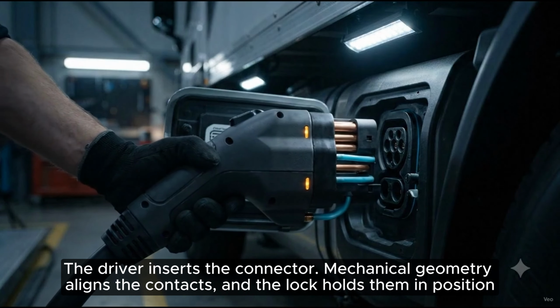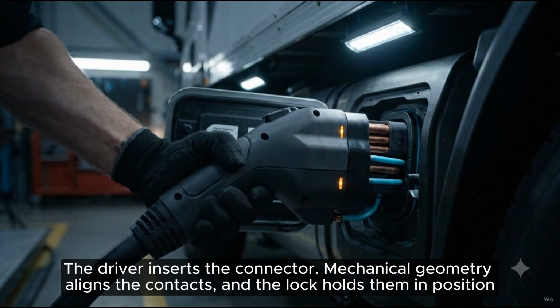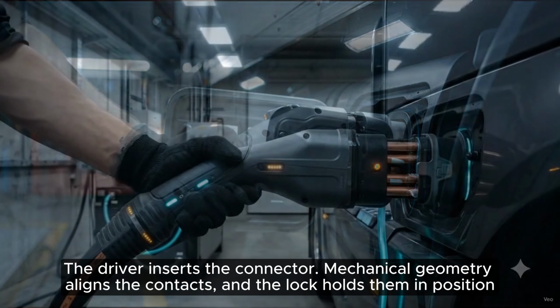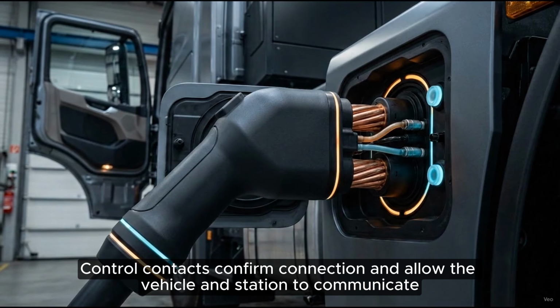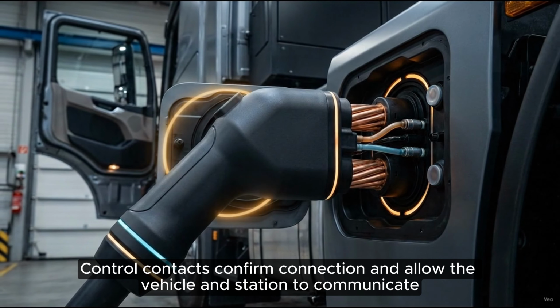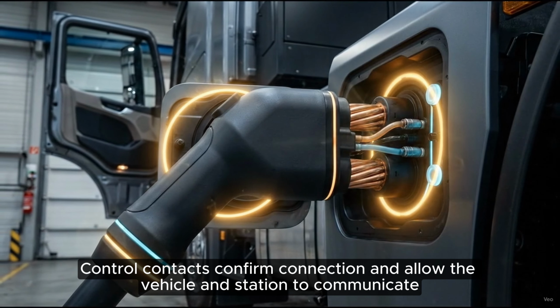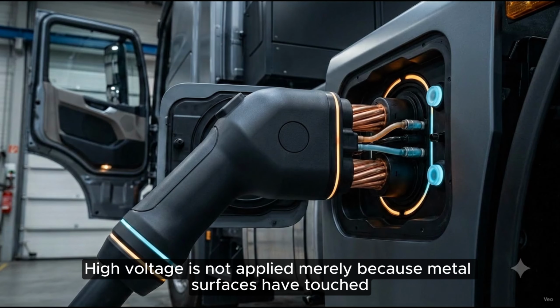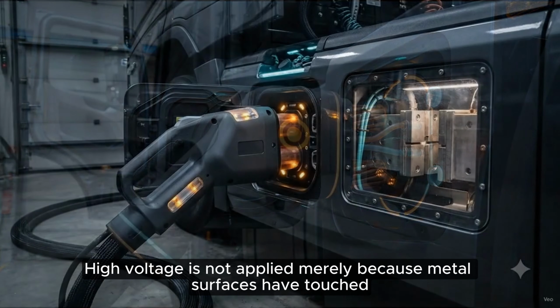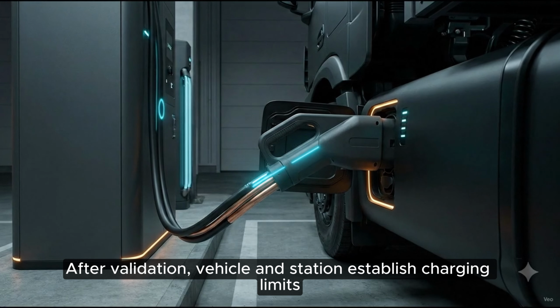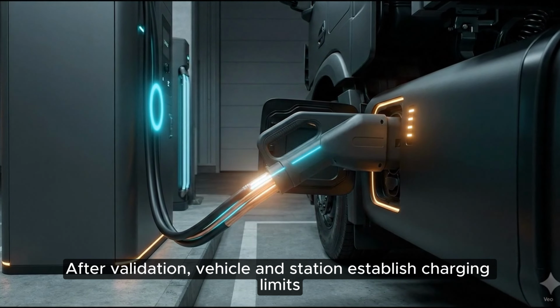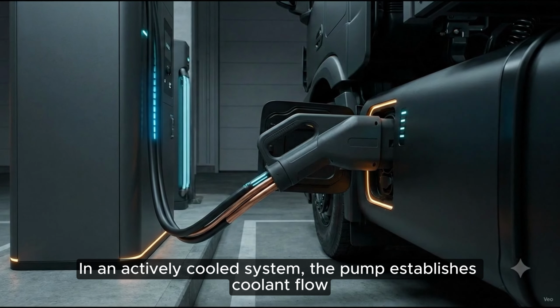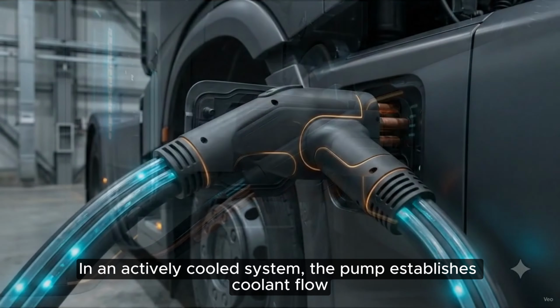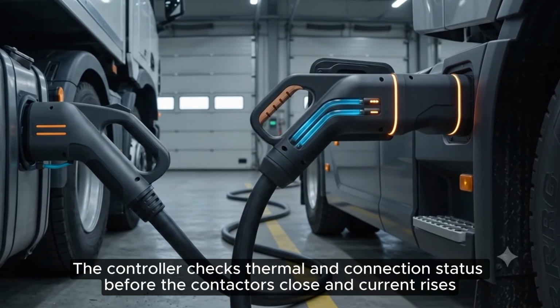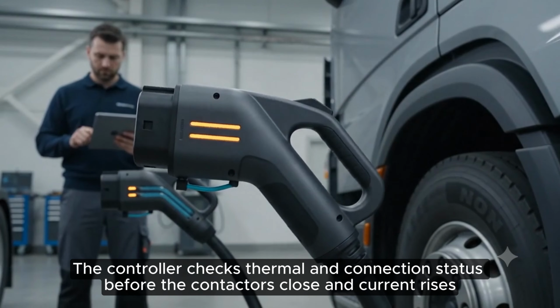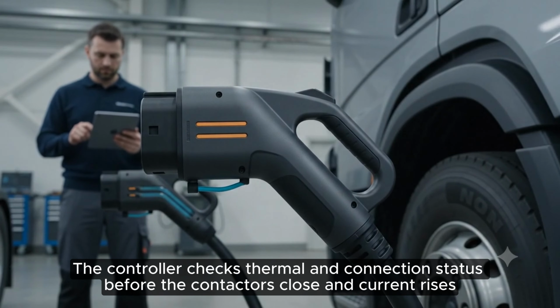The driver inserts the connector. Mechanical geometry aligns the contacts, and the lock holds them in position. Control contacts confirm connection, and allow the vehicle and station to communicate. High voltage is not applied merely because metal surfaces have touched. After validation, vehicle and station establish charging limits. In an actively cooled system, the pump establishes coolant flow. The controller checks thermal and connection status before the contactors close and current rises.